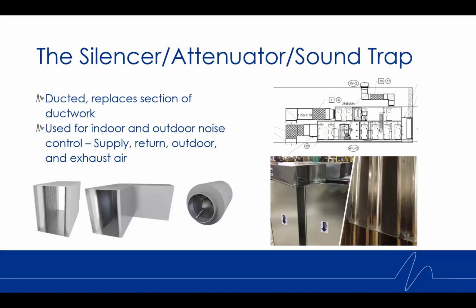So now we'll take a look at a couple of the products that we use to mitigate these sounds. If we're looking at some sort of ducted air path, so this would be your supply, your return, your exhaust or outdoor air path, we're typically going to use something called a silencer. You might hear this called an attenuator or a sound trap. It's essentially a sheet metal piece designed to replace a piece of duct, with baffles in the interior to absorb some of that noise.